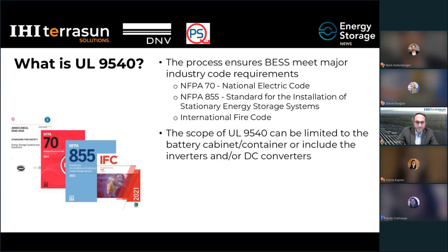UL 9540 can be applied specifically to battery cabinets, or it can also be used to include the inverters and DC converters for systems that are either AC coupled or DC coupled. As an integrator, when working on projects for 9540 compliance, it's important to review all of the safety features that will allow that system to operate properly and protect life safety and land safety and personnel. So to do that, a safety analysis must be created, and within that safety analysis, you need to have a hazards mitigation analysis and failure modes effects analysis. And in follow-on slides, I'll show examples of what those look like and what goes into them.